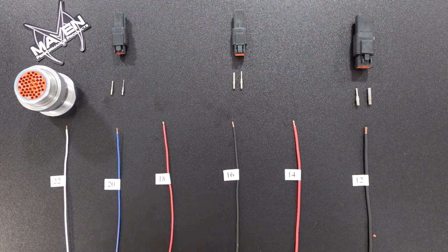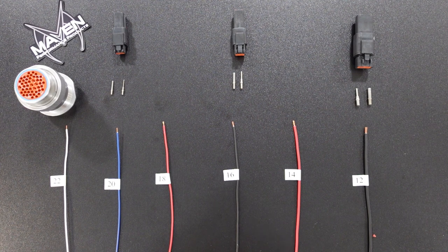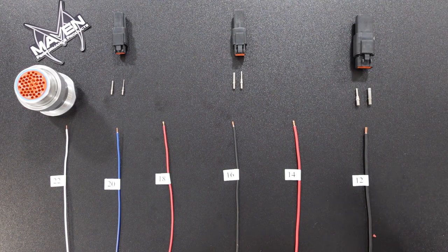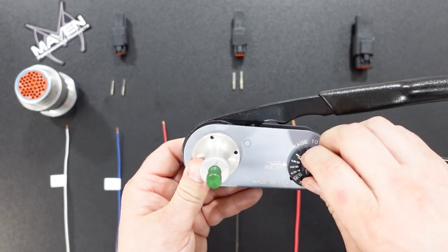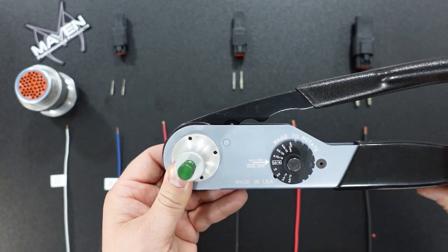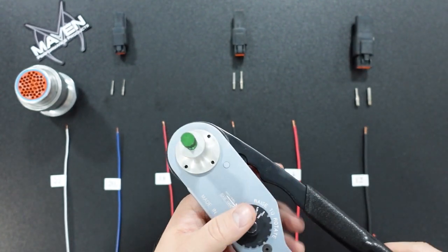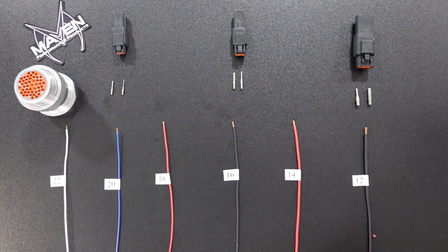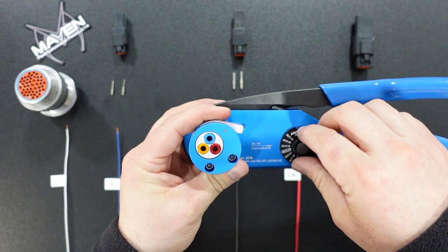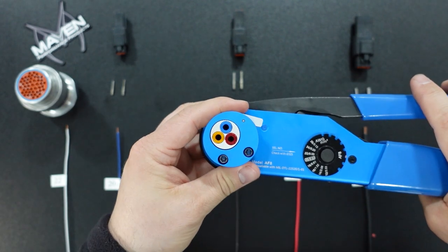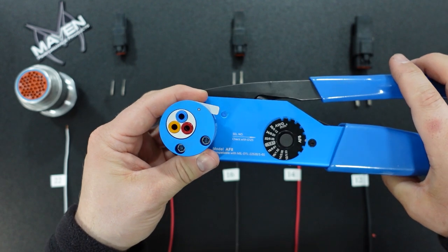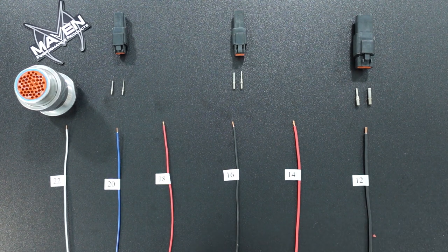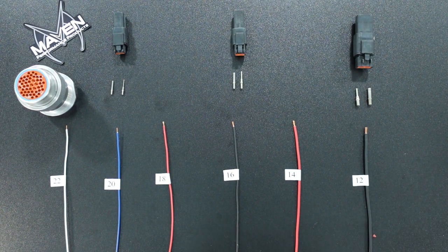Let's just recap a standard way to crimp the solid terminals. Let's say if you have a 16 gauge wire, you can simply use a 16 gauge pin socket for your setup. And when you use your crimpers, you're going to dial this to a 16 gauge, and then you will set the depth accordingly. If you're not familiar with that, check out some of our other videos showing how to do that. You're always going to set the dial to the wire gauge and set the turret up accordingly. Same thing with the 20 or with the 12.